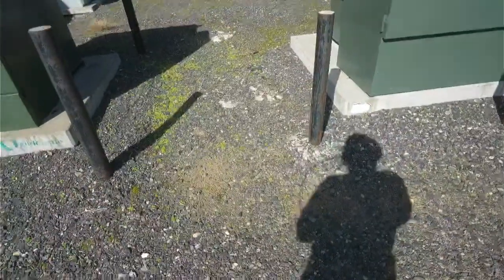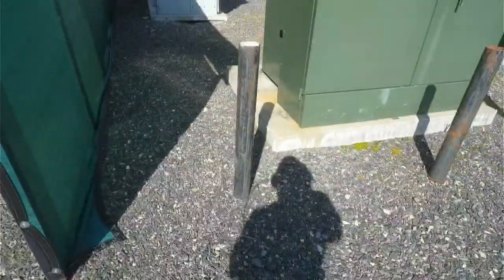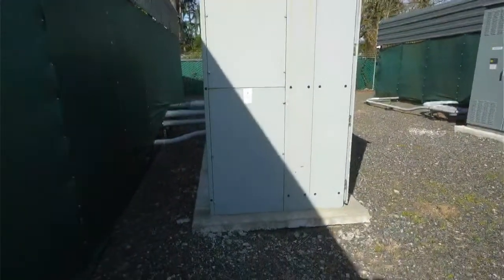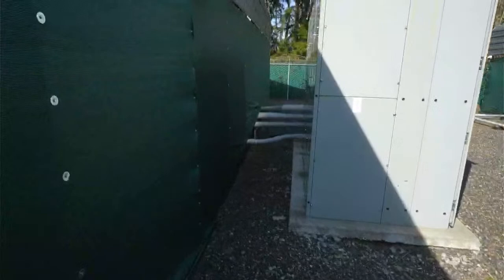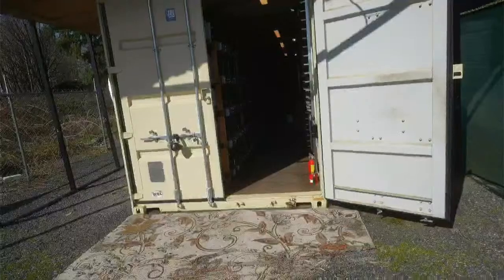So the power lines are coming in at 14,000, I think 460. I think that's the voltage coming from the power lines. They're all underground, by the way, running to this transformer and to this transformer. Then it transforms it to 208, well, 120 technically on the phase, and sends them off to the gear over here. You can imagine underground wires running to this gear. That gear has the breakers in it, and that transformer also runs to that gear. Then those PVC pipes right there are what actually run to our 600 amp panels. So that gives you guys an idea of how that whole process works.